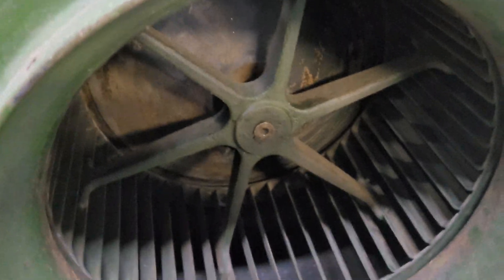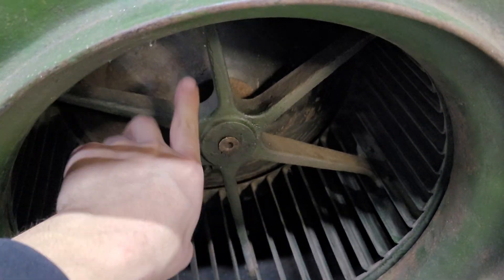You can see here, there's the blower wheel. It has a six-spoke cast iron hub. The bearings in the B-30 are a little rough. And here's the inside of it. Now we'll take a look at the B-25 — that's got a three-spoke hub. That one's a little smoother.